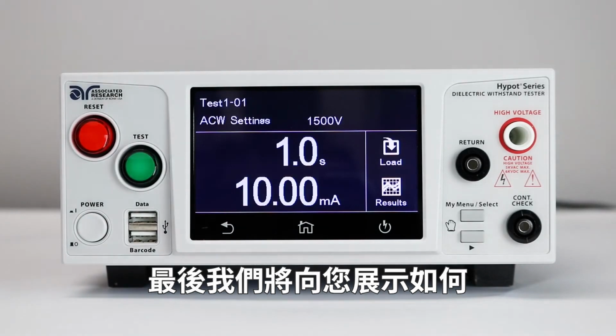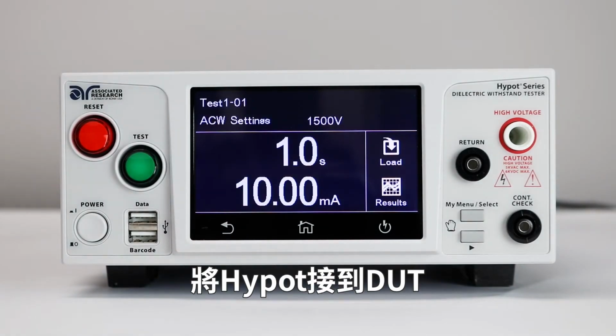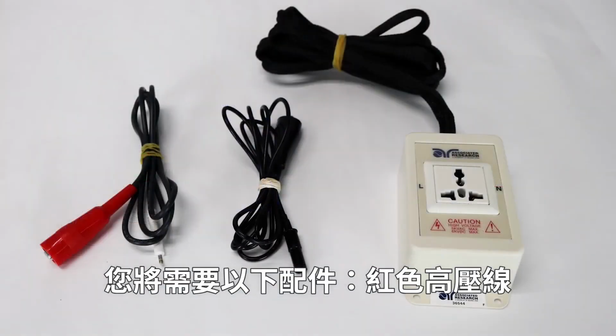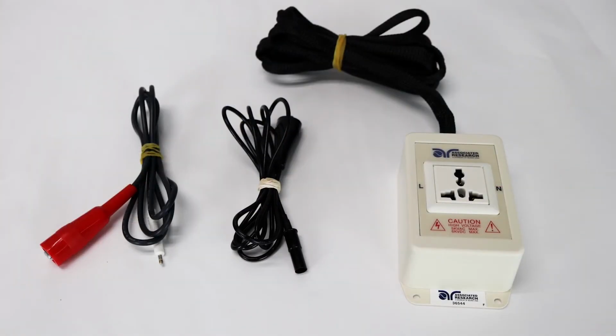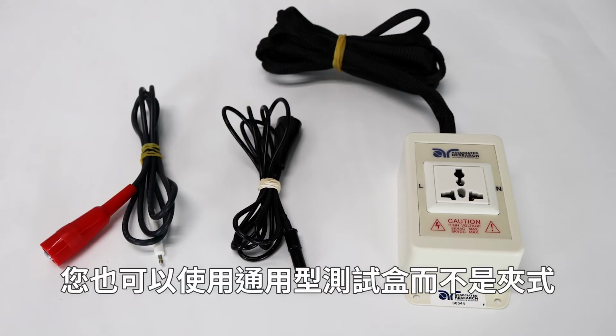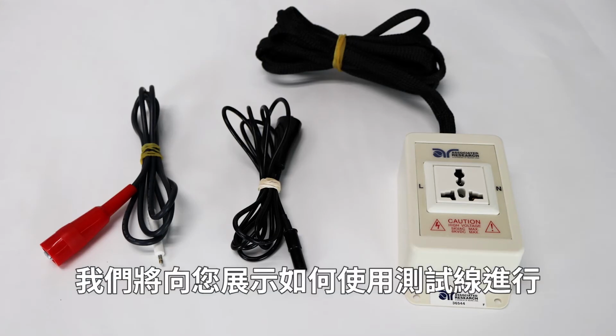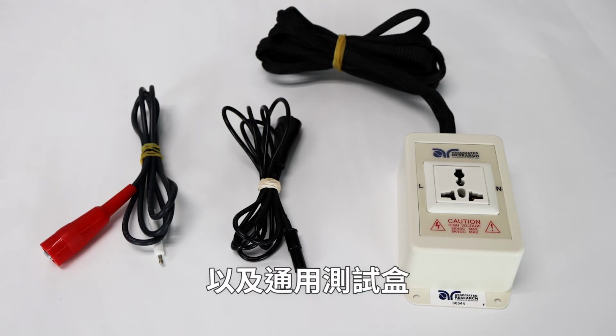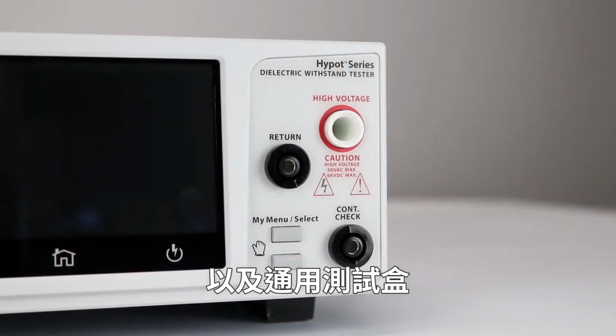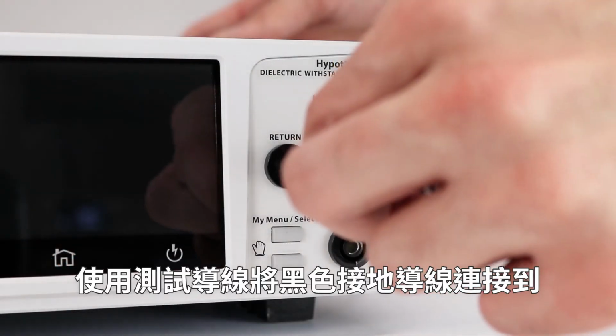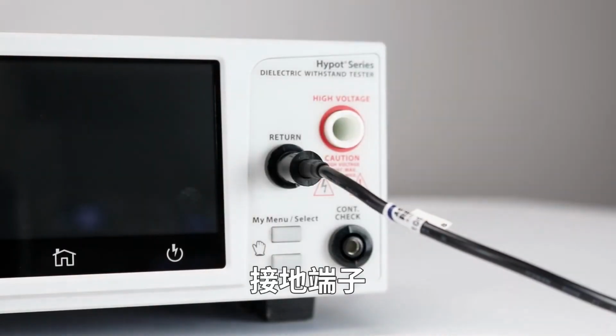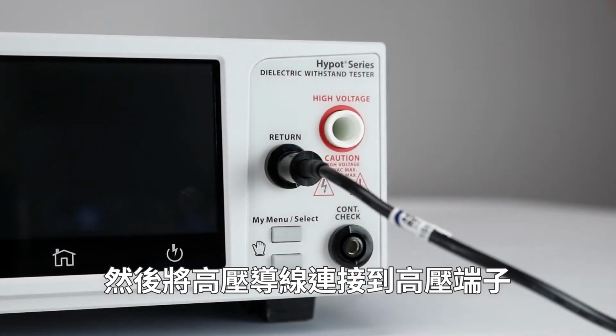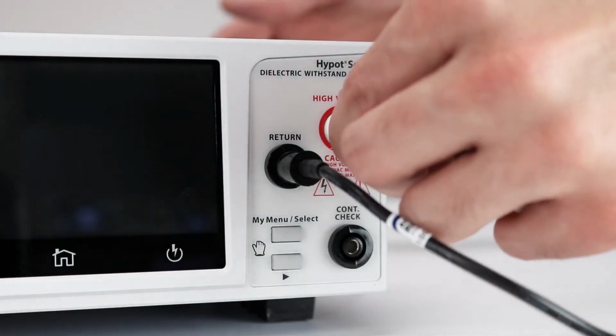Finally, we're going to show you how to connect the Hypot to a DUT and run the test sequence. You're going to need the following accessories: red high voltage lead, black return lead. You can also use the universal style adapter box instead of the clip leads. We're going to show you how to make test connections using the test lead as well as the universal adapter box. Using test leads, connect the black return lead to the return terminal. Then connect the high voltage lead to the high voltage terminal.